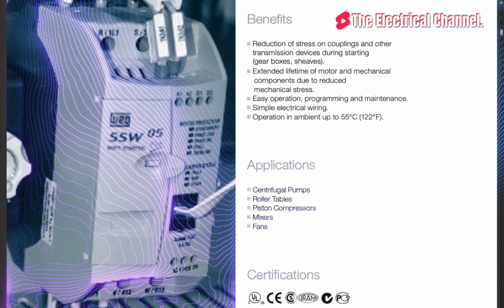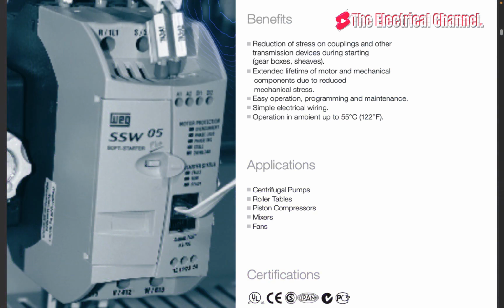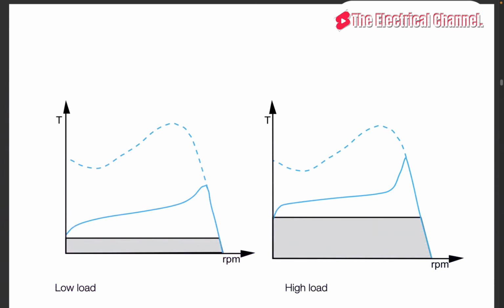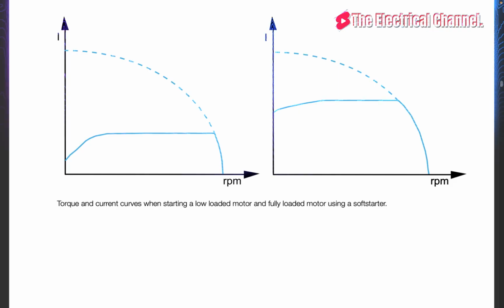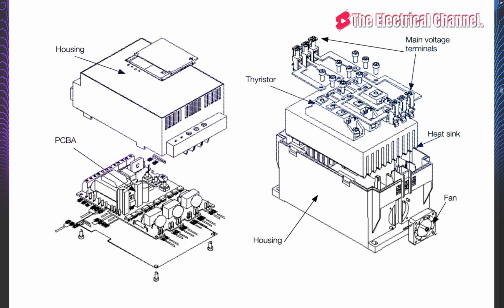Depending on the application, the start can be short or long. Since the current is higher during the start, the soft starter will warm up during the start. It is very important to select a soft starter with thyristors and heat sinks dimensioned for the motor and the start performed.